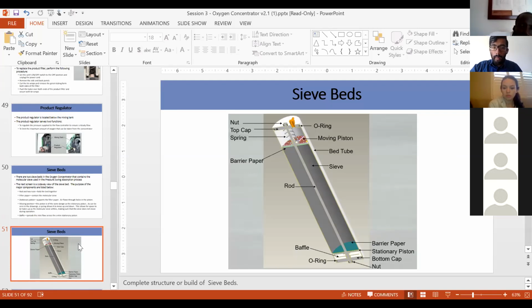Yep. When your sizing changes, you're going to get high pressure or low pressure. But if you are getting the same sizing, it shouldn't have any problem. At the same time, you can use the old unit. You can open up that particular unit and replace the raw material of the sieve, replace it and seal it properly, and it will work. But if you're using the wrong size, that can cause a pressure difference in the system. That can cause a low alarm and a high alarm.